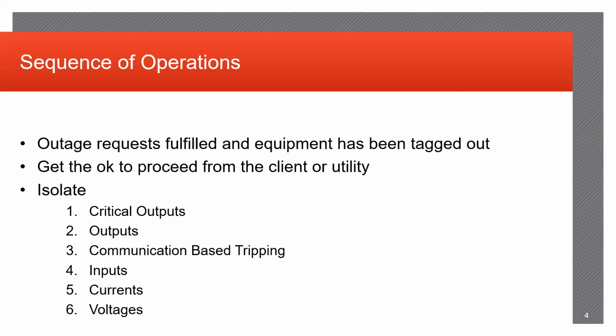Just a quick overview of the sequence of operations. The isolation procedures steps always take place. You always start by isolating your critical outputs. This may be any trips to breakers, circuit switchers, any form of in-service equipment. This is done specifically first to avoid the relay assuming that a loss of current or voltage source may cause a misoperation. Any other outputs, this could include alarms coming from the relay as well. Those will be isolated next. Communication-based tripping, this may be direct transfer trip, any other POTT schemes, stuff like that. Any inputs coming into the relay will be isolated next, and then to follow up, your currents and voltages will come last.